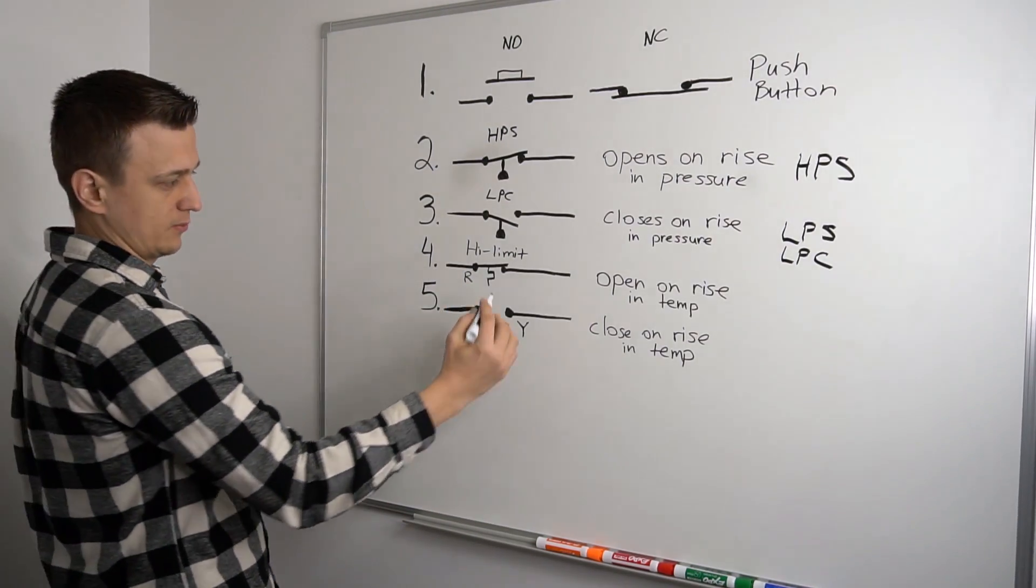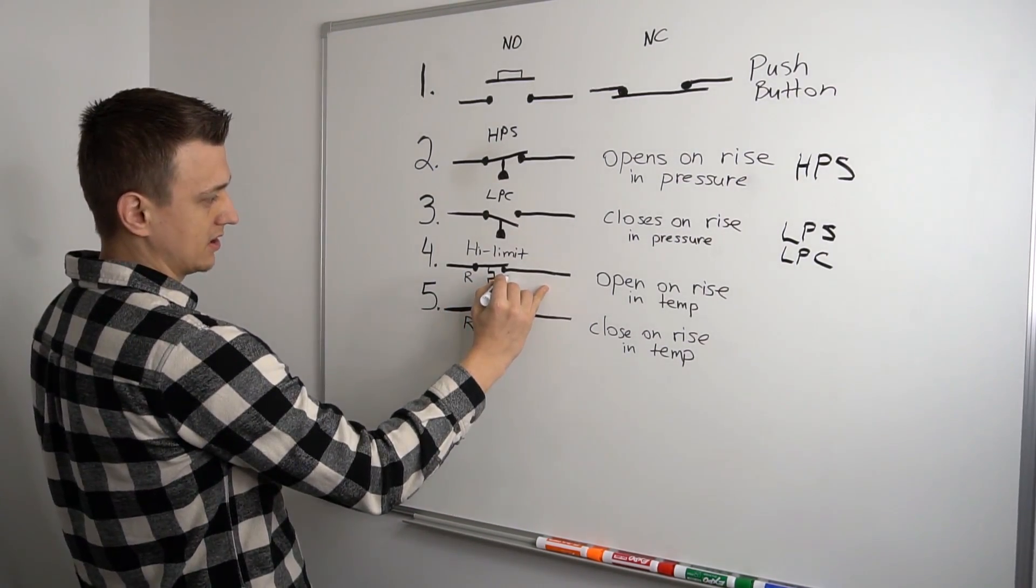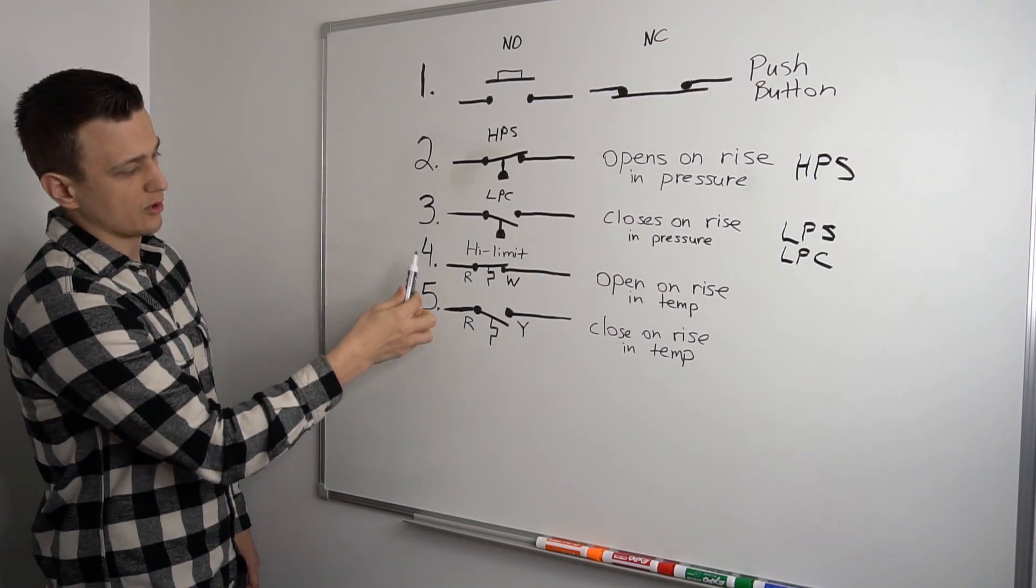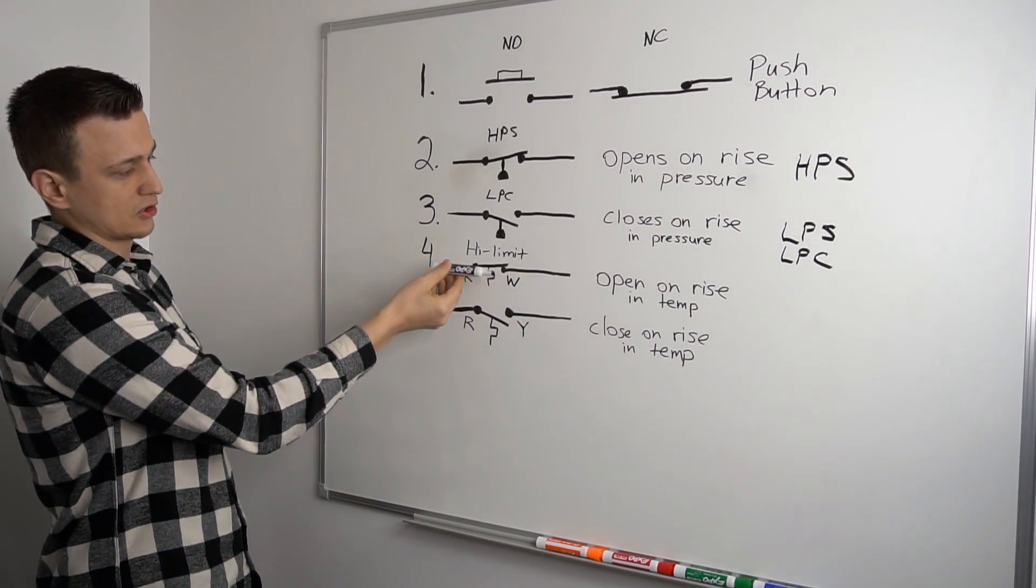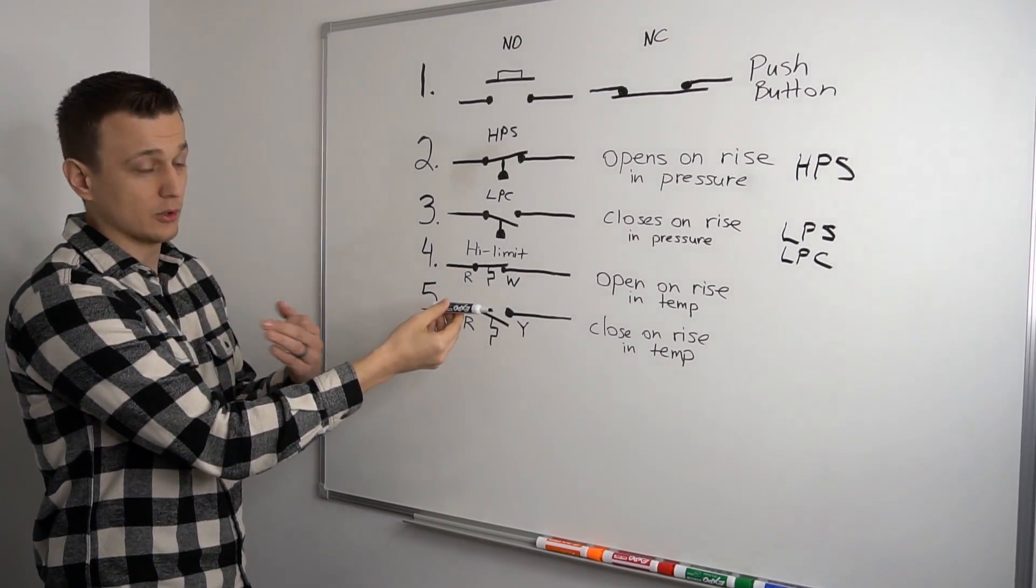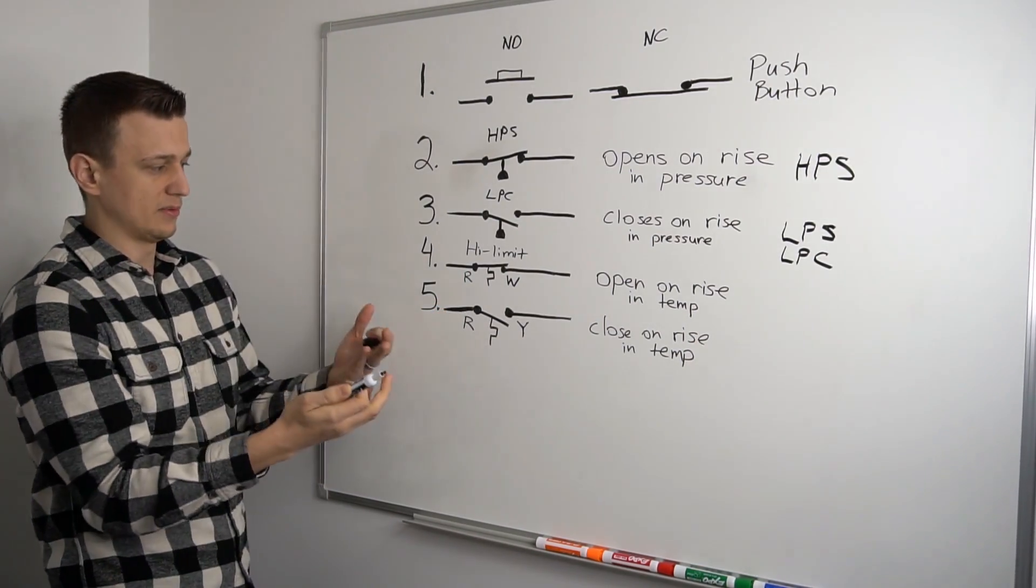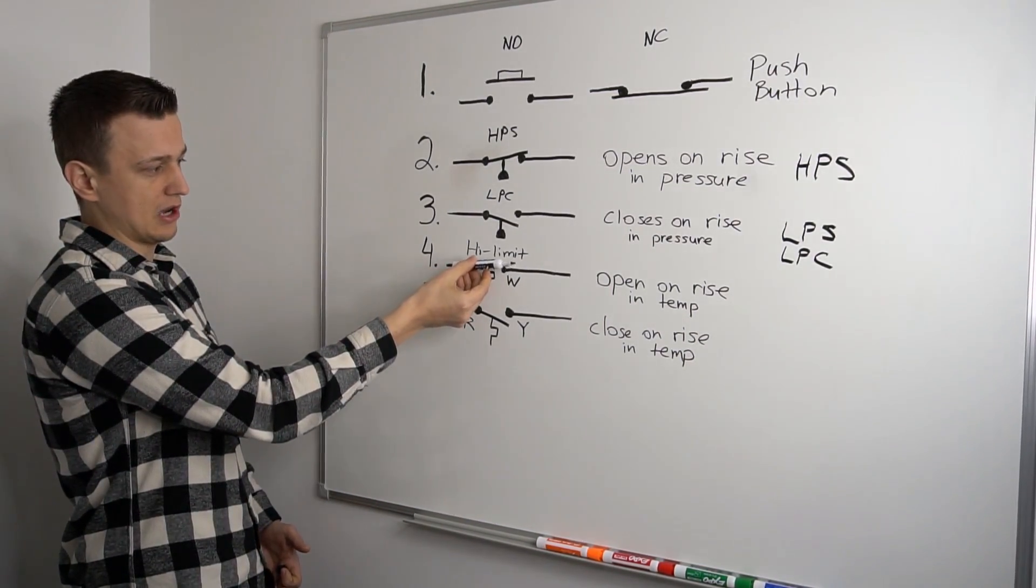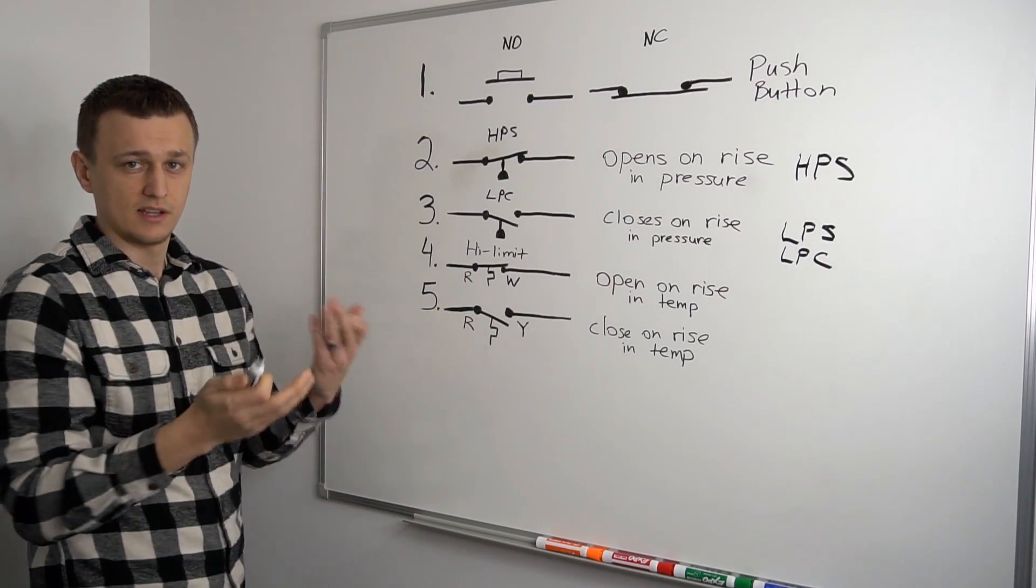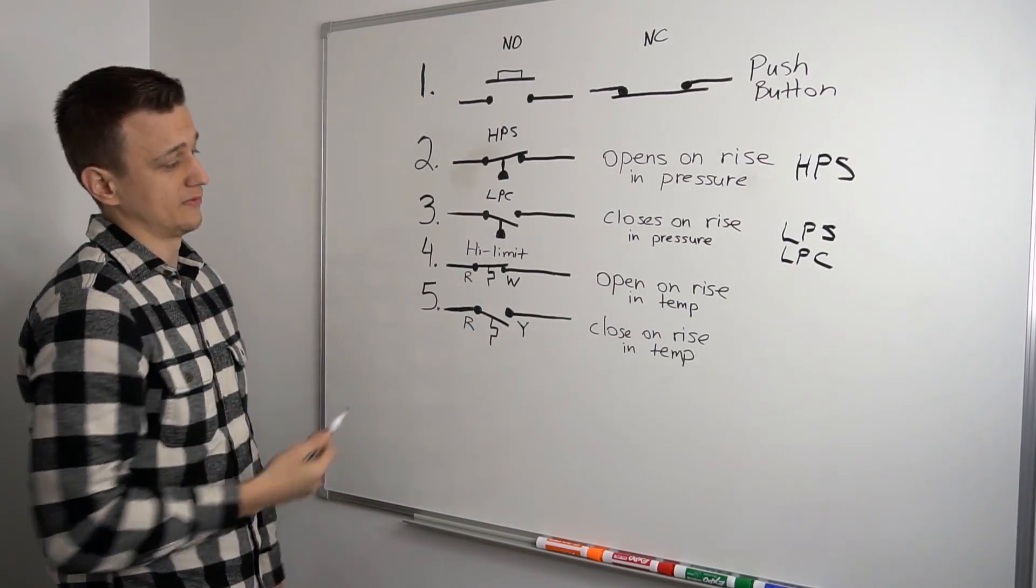Similarly, in the winter, when your furnace is running, this would be W. When your furnace is running, this is closed. If the temperature in the house is getting hotter, the thermostat senses that temperature. And this switch goes up and opens up, interrupting the circuit and turning off the furnace.